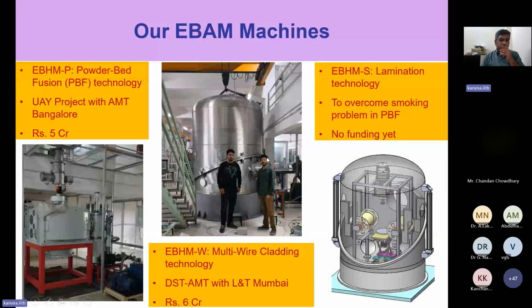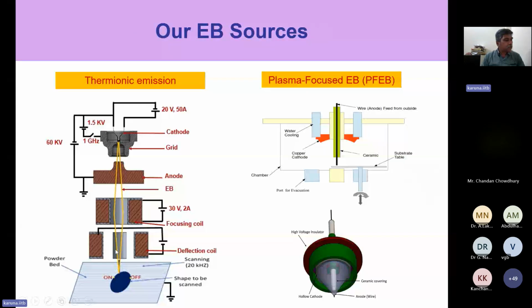Okay, so let me once again explain the principle because we have just 15 minutes left. So what we do is called thermionic emission. Any body above 0 Kelvin will emanate electrons. When its temperature increases, then the amount of electrons emitted will be much higher. That's a very simple concept. So what we do is we have a small tantalum filament. As you see in the bulbs, you have a filament. So small tantalum filament, we apply something like 1000-watt power. At 20 volt itself, it gets enough energy and 50 ampere current. So within about 1000-watt power, it becomes red hot, and then it emanates electrons.